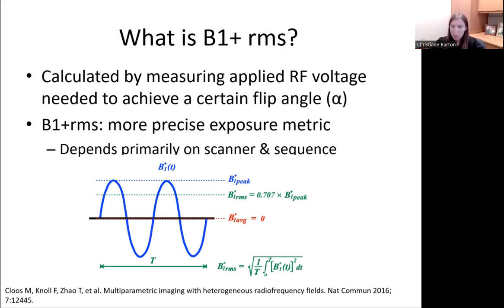B1 plus RMS can be thought of as the supplemental metric to SAR for controlling RF power deposition. Most modern scanners report this value along with SAR for each sequence, but scanners produced before 2013 will probably not. B1 plus RMS is a more precise exposure metric because it depends primarily on the scanner and sequence and less on the patient than SAR.